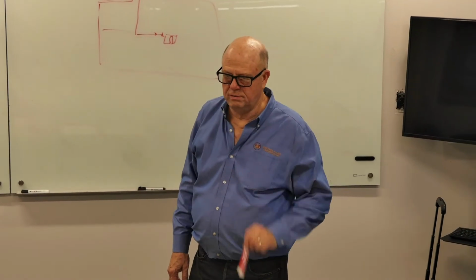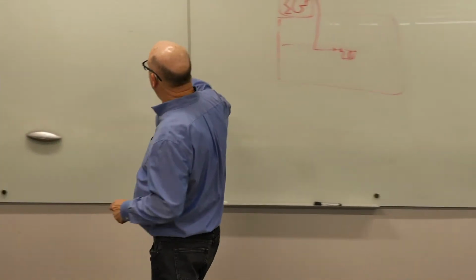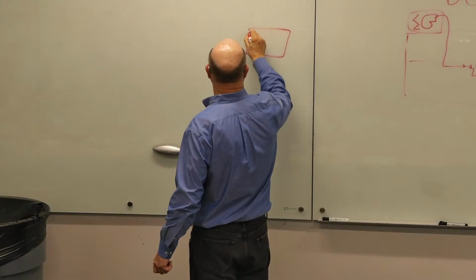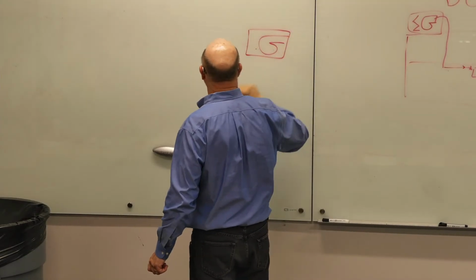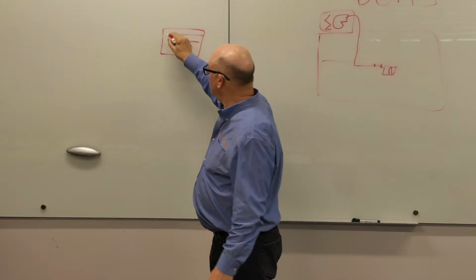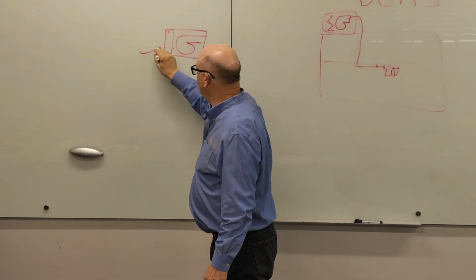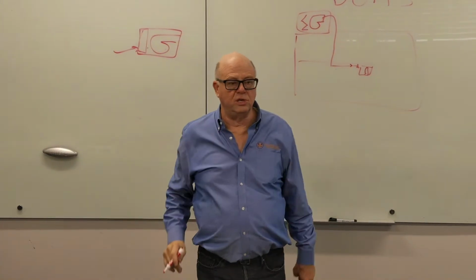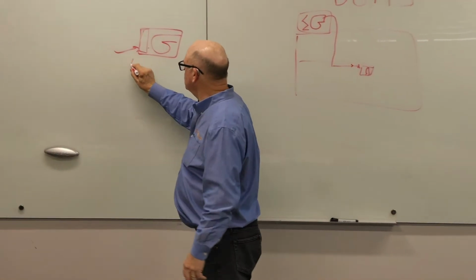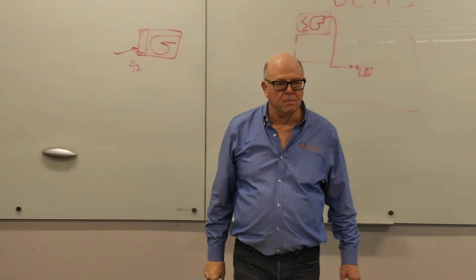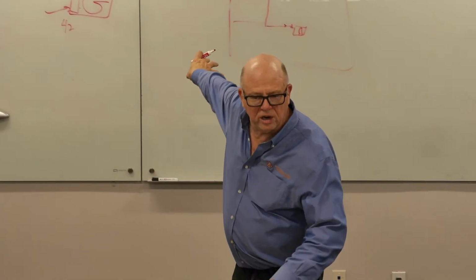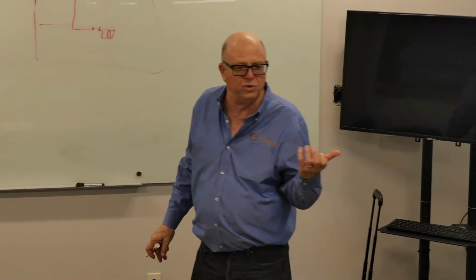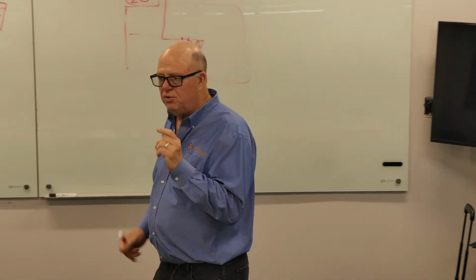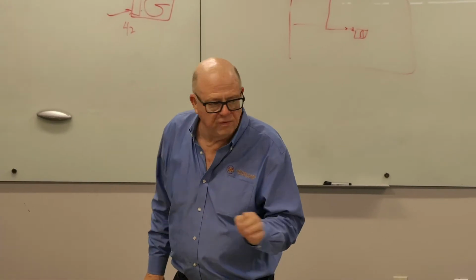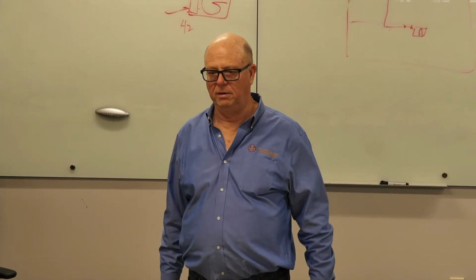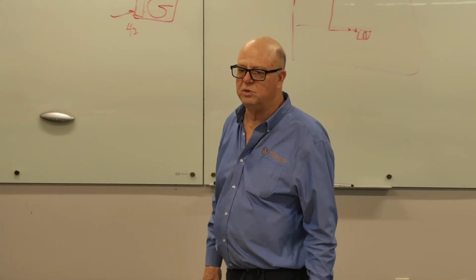VRF doesn't do that. We'll talk more about it in the next series when we talk about mechanical refrigeration. But you've got a cooling coil, and you've got liquid refrigerant that's coming in, and after it goes through the expansion valve, at design conditions, it's probably about 42 degrees. So far, this looks just like our chilled water fan coil, only we're doing it with refrigerant. But if you look at the energy efficiency ratings of VRF, they're unbelievably high. In fact, when they first started being published in the US, we just all called them liars.